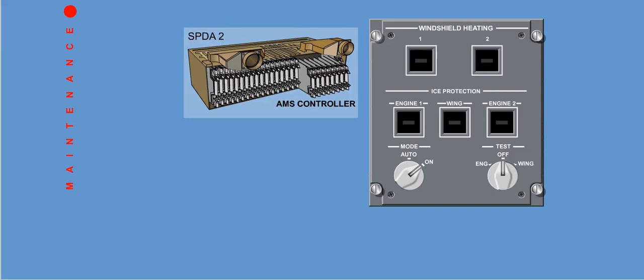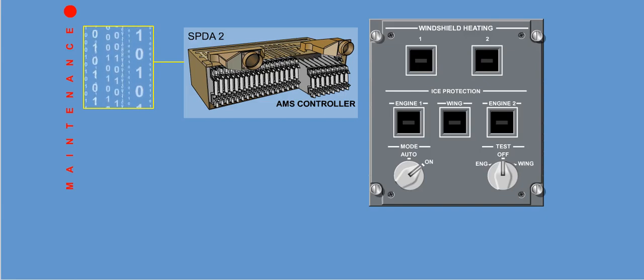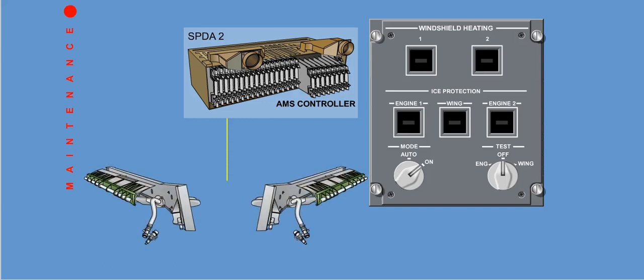The desired skin temperature is calculated as a function of slat position, ambient temperature, Mach, and altitude in the range of 71 degrees Celsius, 160 Fahrenheit, to 121 degrees Celsius, 250 Fahrenheit. The AMS controller calculates the desired skin temperature to determine a duct reference pressure. The controller then compares the calculated and actual duct pressures measured by the pressure sensors. The AMS then modulates the pressure regulating valves by increasing or reducing the torque motor current.